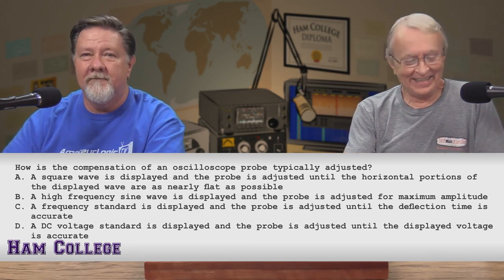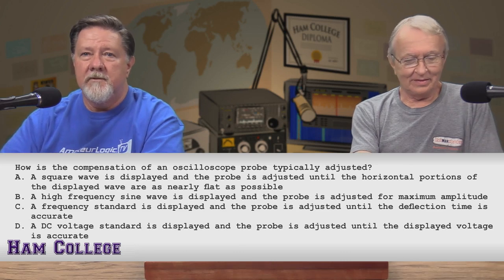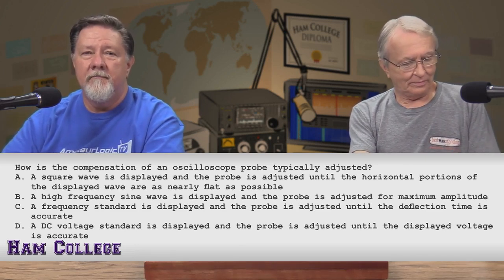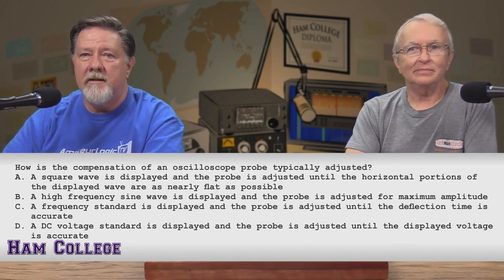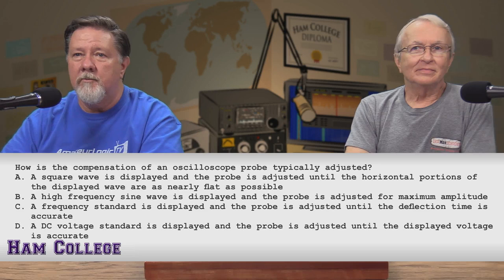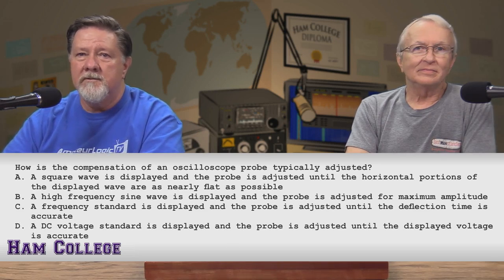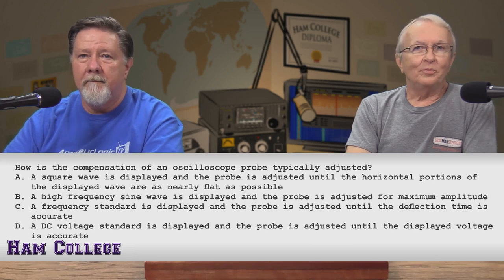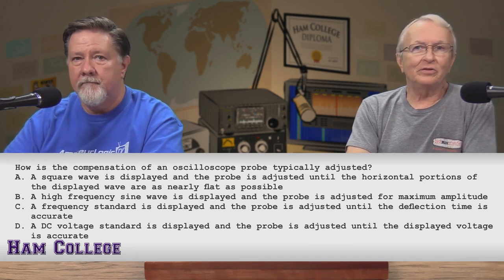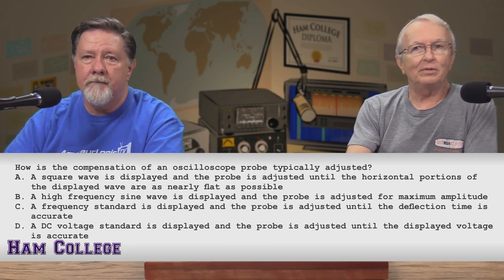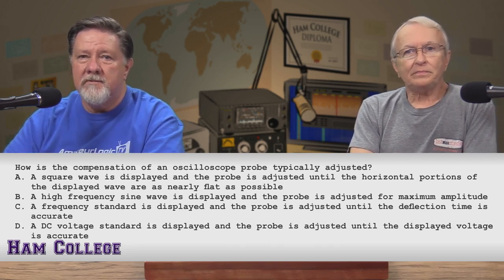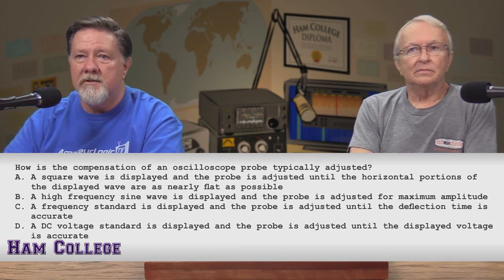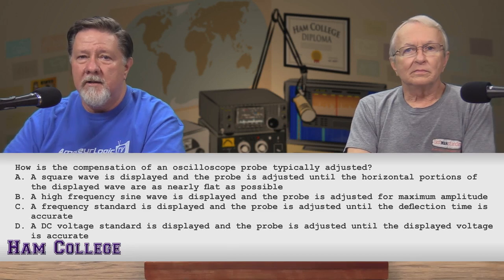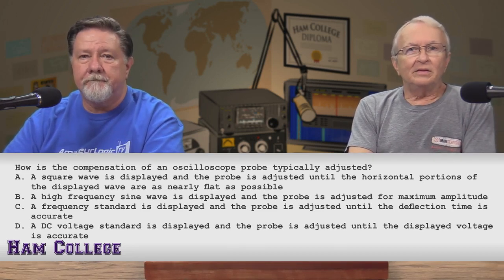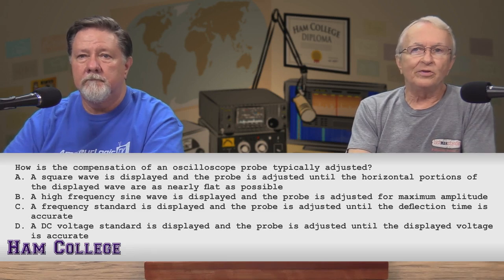How is the compensation of an oscilloscope probe typically adjusted? A, a square wave is displayed and the probe is adjusted until the horizontal portions of the displayed wave are as nearly flat as possible. B, a high-frequency sine wave is displayed and the probe is adjusted for maximum amplitude. C, a frequency standard is displayed and the probe is adjusted until the deflection time is accurate. Or D, a DC voltage standard is displayed and the probe is adjusted until the displayed voltage is accurate.